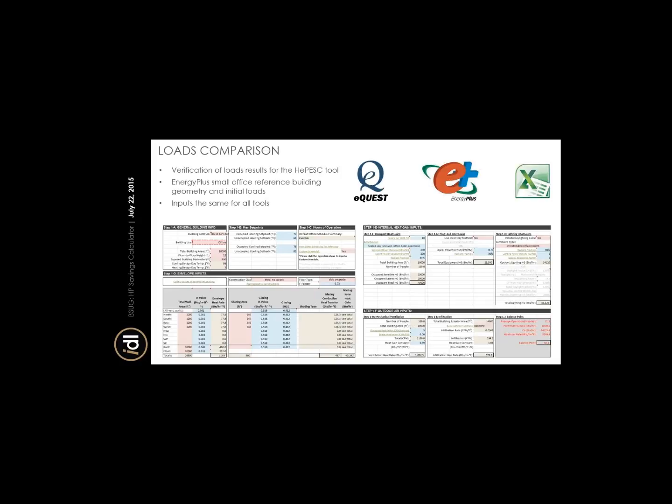And so what we wanted to do with the tool built was go back and check, okay, we need to verify we're getting out what we're expecting to. We started with taking some existing projects and existing simulations for all 3 system types, the air source, water source, and VRF systems, and trying to back plug in that design into our tool and compare the results. What we found from that was the simulations are so detailed, it's really hard to go back and find all the inputs that you would need.